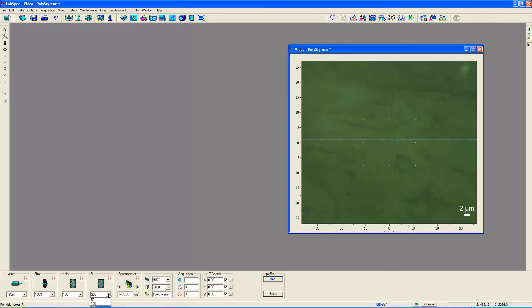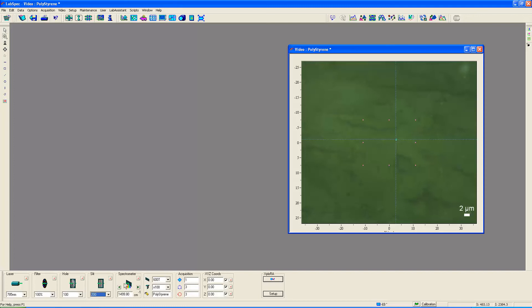A modest slit size, well the largest slit size of 200 micrometers, because we don't really need the spectral resolution as you'll see in just a moment. I have the grating set to 1500 reciprocal centimeters, and by that I mean to say that the very center of the detector, the CCD, that pixel will correspond to this Raman shift in reciprocal centimeters.